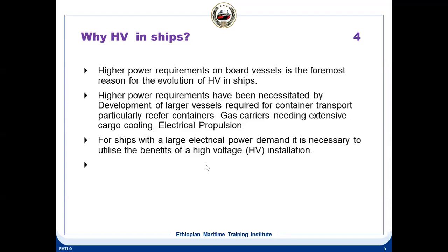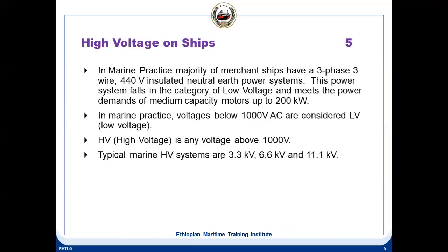So why are we going for high voltage? Basically, the development of larger vessels like container ships carrying reefer containers, gas carriers, or ships needing electrical propulsion. Those ships need high voltage. In marine practice, the majority of ships have three-phase, three-wire, 440-volt insulated neutral earth systems. So most ships you will find are 440-volt, neutral insulated, three-phase, three-wire systems. This power system falls in the category of low voltage and meets the power demands of medium capacity motors up to 200 kilowatt. In marine practice, voltages below 1000 volts are considered low voltage, and high voltage means any voltage above 1000 volt.